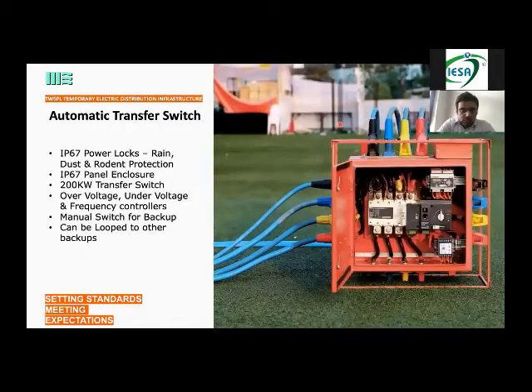This is the transfer switch we are using as of now. Over here, if you see my pointer, this is your main genset. These are the power locks, and I'm going to talk about what power locks are. The main genset is on the left-hand side, the backup is on top, and the power is going from here. In these changeovers, what we have done as a company is that we can loop these changeovers. So in an event, if you have a sound, light, LED or something which is important, you can loop these changeovers also.